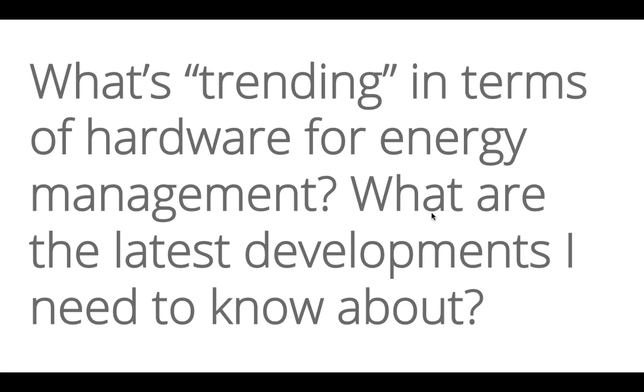Yes. Today's trend is to develop a measurement plan. For example, in case you want to implement an energy management system with ISO 50001 certification. I hope you know this ISO certification. For that, you have to set up a measurement device at the main panel, but also on the division boards. And to get relevant data, it's important to measure accurately electrical parameters like energy and power parameters, and different and numerous kinds of loads: motors, lighting, heating, and so on.